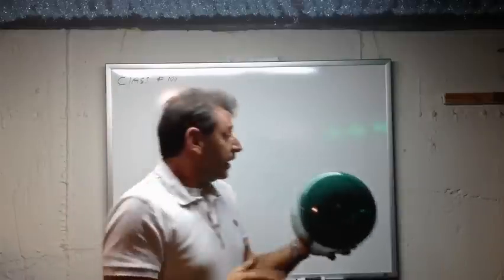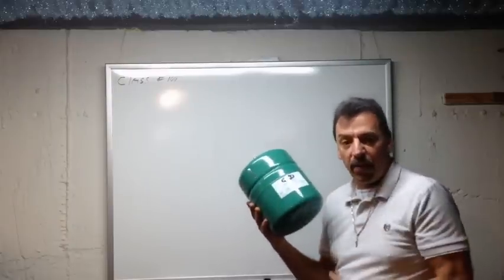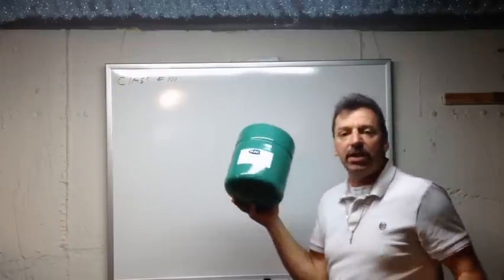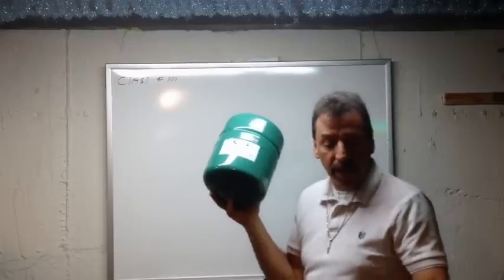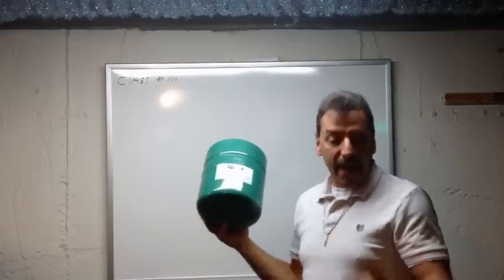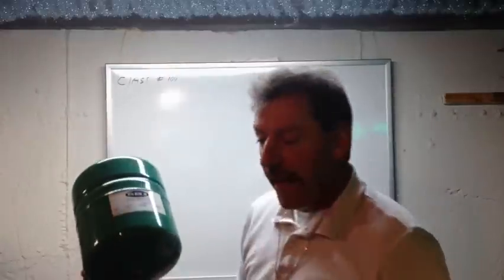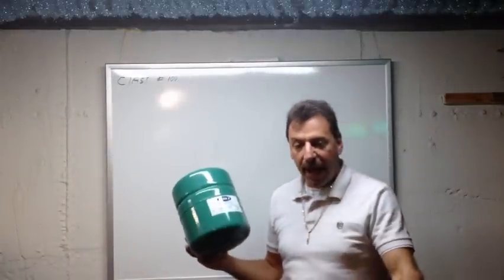When these go bad, the boiler will release pressure out the relief valve also because the water, as it expands, has nowhere to go. And it's a simple test. You'll know when these go bad because if it's dripping water and the flame is on under the boiler, the fire is actually on and it's firing, that's when you'll get the water pressure releasing out this relief valve here. As the boiler goes off and the water cools, that will stop.